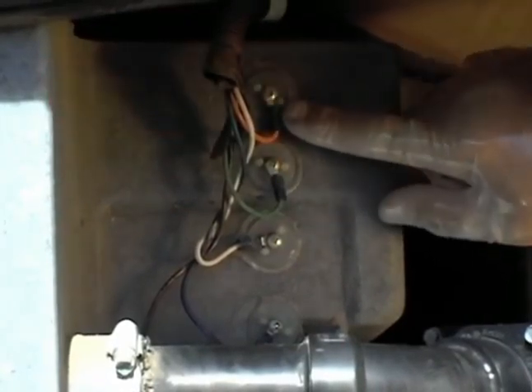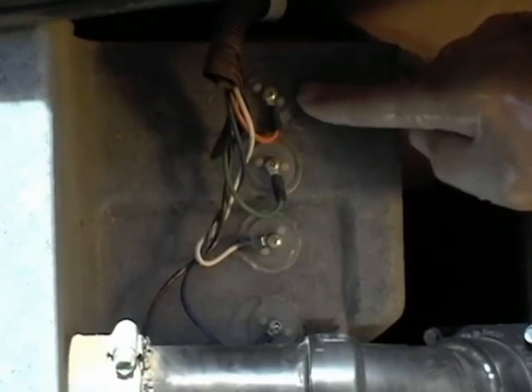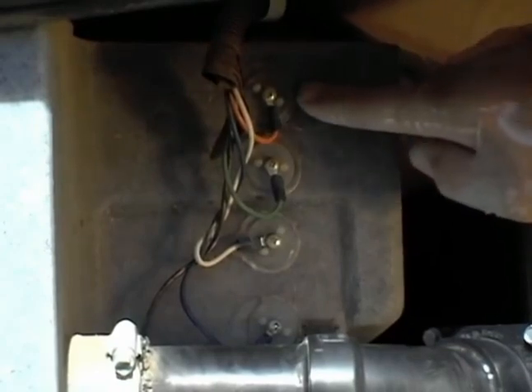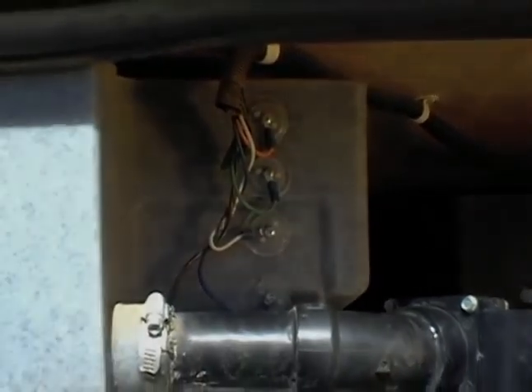I'm telling you this because if you don't clean the sensors once in a while in both tanks, you get a buildup of stuff on them, and the panels will give you a false reading or read full all of the time.